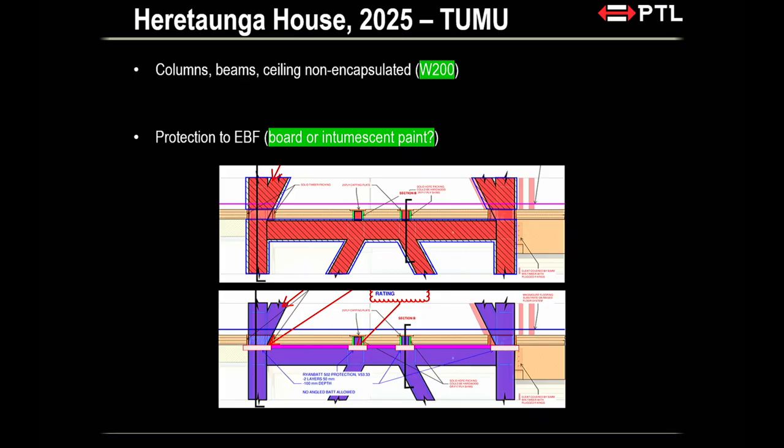Now, if you go intumescent paint, right, you can intumesce and paint the EBF, no problem. But then you're left with all these holes because, again, you have that I section going through, and now you have a brace coming in. So this particular hole over here is not that easy because previously with the Arvida project, the hole was just nice and square, right? So you can fit the bat in there, you put some mesh stake, will stay in place. But in this case, around this angle, you have to shave off a bit of a bat and stick it up, and it just doesn't stick.